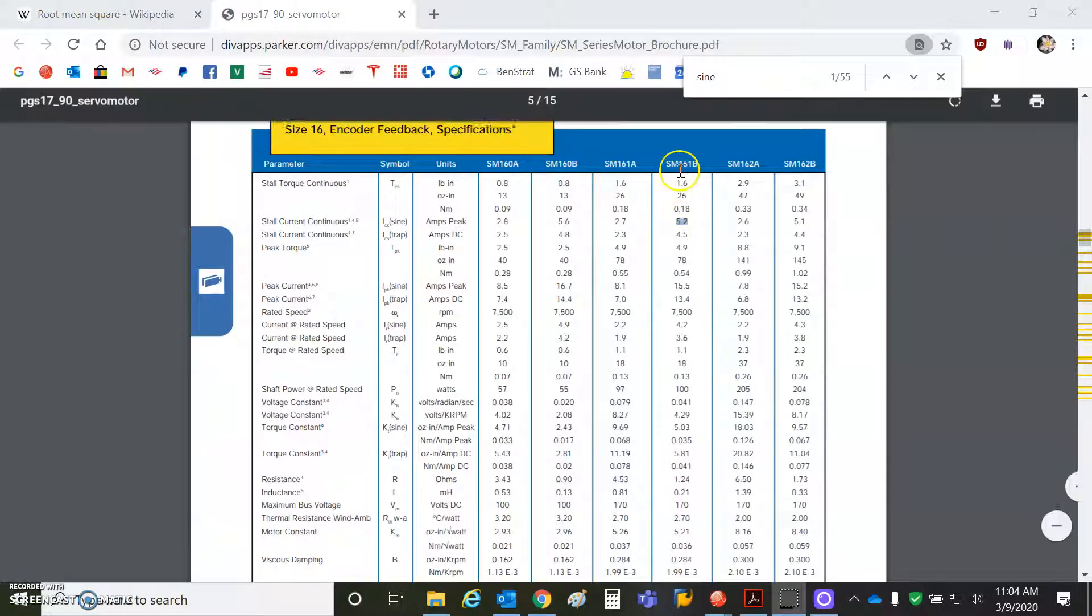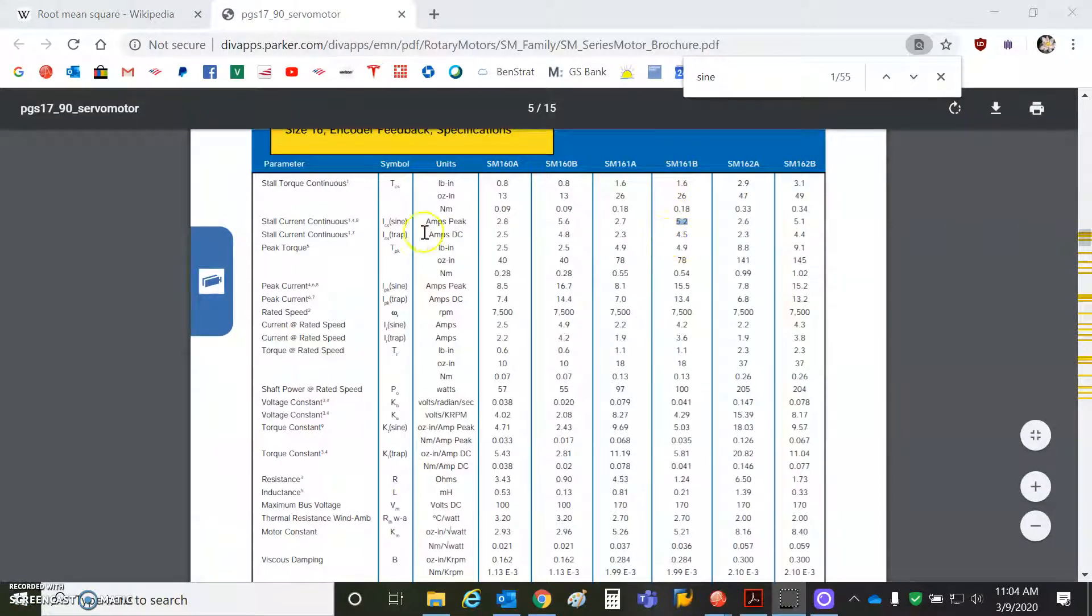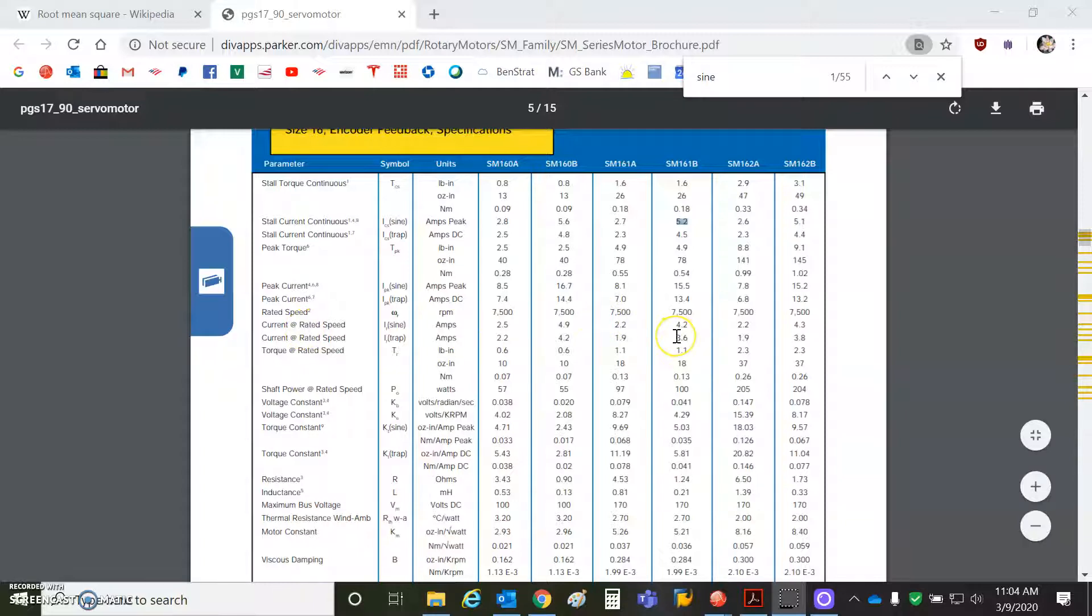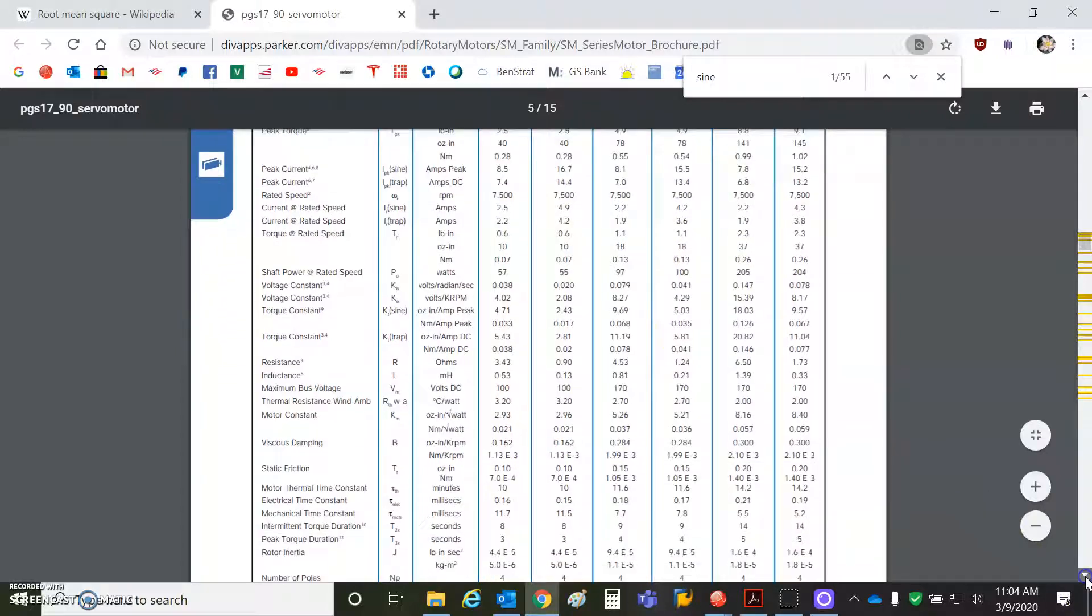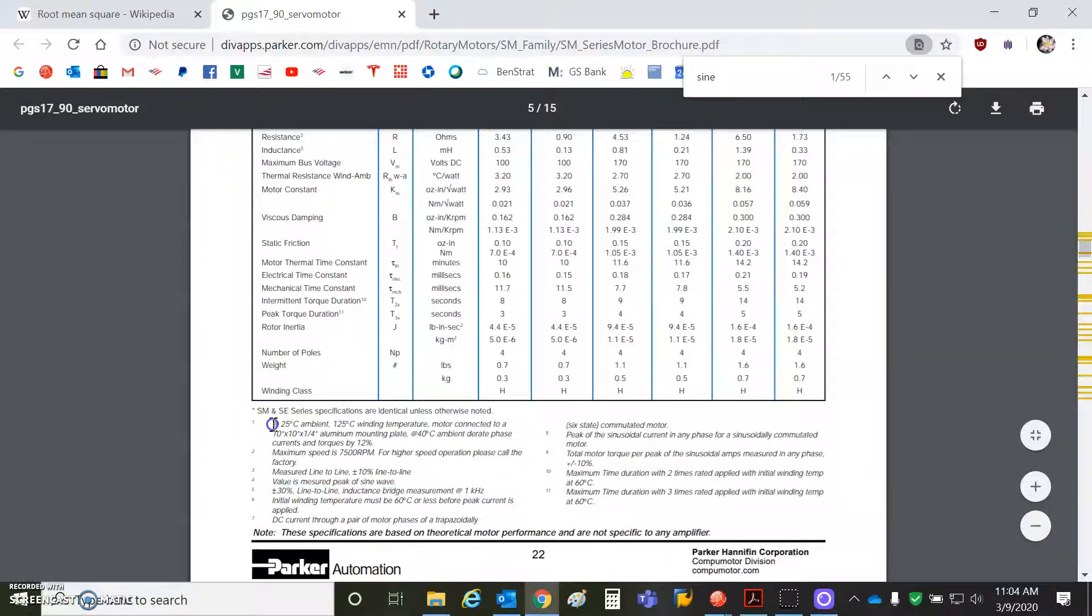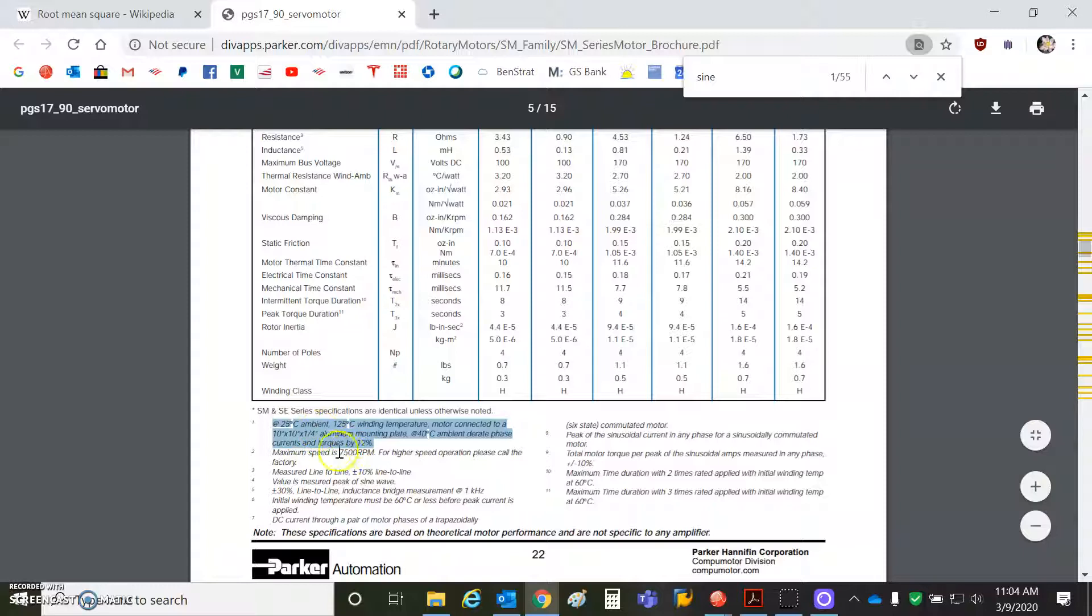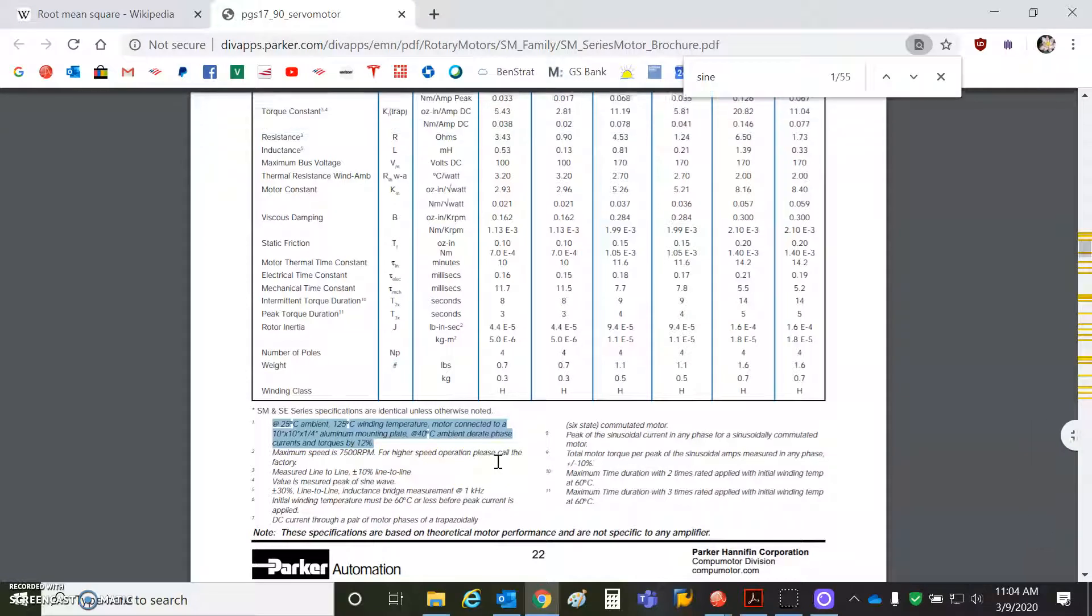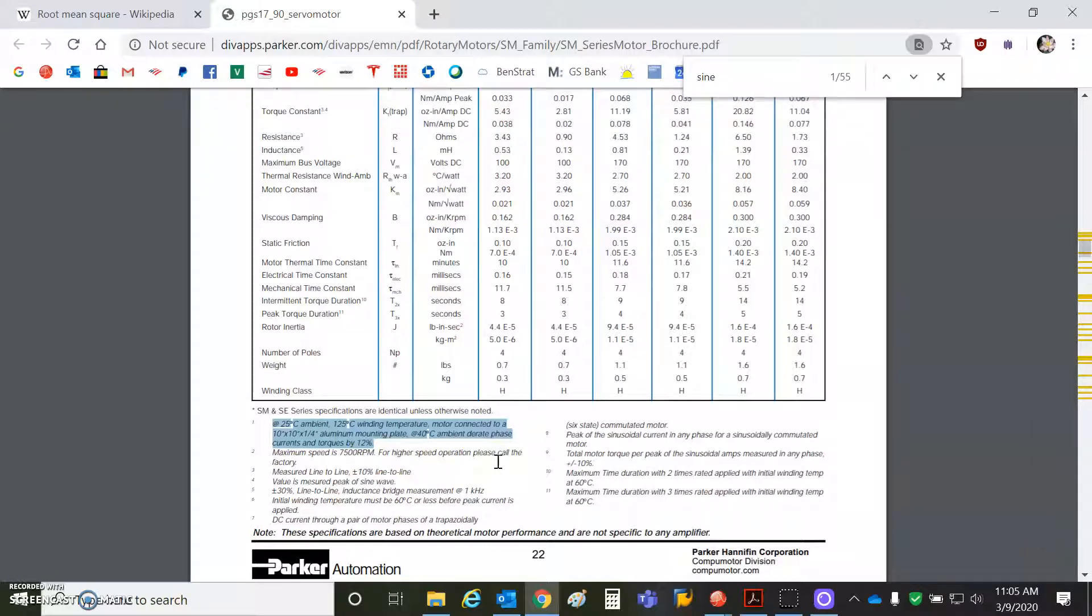So we're going to look at my little size 16 motor here. Again, it says amps peak sine wave, so that's not exactly the RMS value. That's the peak of the sine wave, and that's the stall current. They also talk about the rated current, trap, and sine. This will be a sinusoidal commutation. So there's a square root of 2 factor in here, too. But an interesting note, note 4, values measured peak of the sine wave. This talks about the motor at 25 degrees C ambient, 125 degrees C winding temperature, motor connected to a 10 inch by 10 inch by quarter inch aluminum mounting plate at 40 degrees C ambient, derated phase current and torque by 12%. So if you don't have any way to get the heat out of the motor and your ambient's high, you still have to be careful.